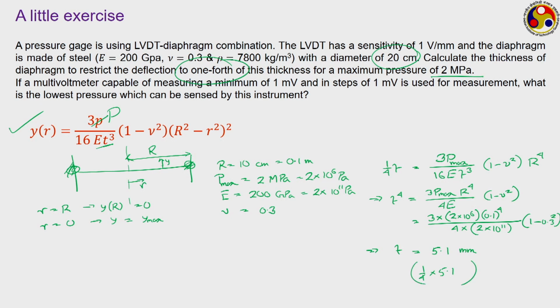Now, go to the next part of this problem, the second part, which corresponds to the secondary transducer. Here we are talking about a multi-voltmeter which we are using to measure the output voltage. So, if a multi-voltmeter capable of measuring a minimum of 1 millivolt and in steps of 1 millivolt is used for measurement, what is the lowest pressure which can be sensed by this instrument? So, we have to calculate the lowest pressure corresponding to this 1 millivolt of output.